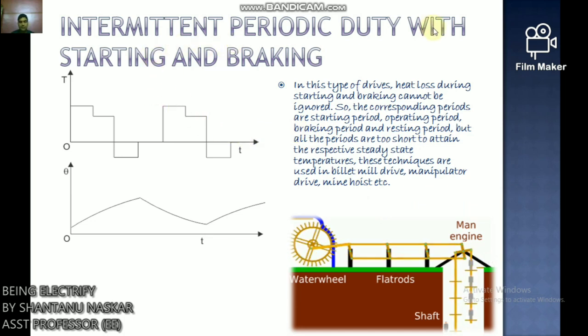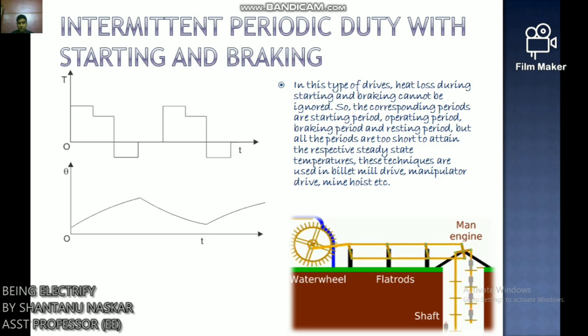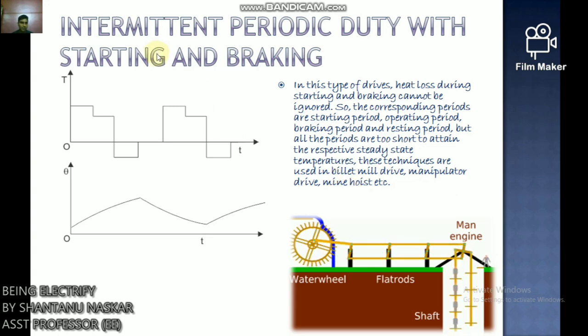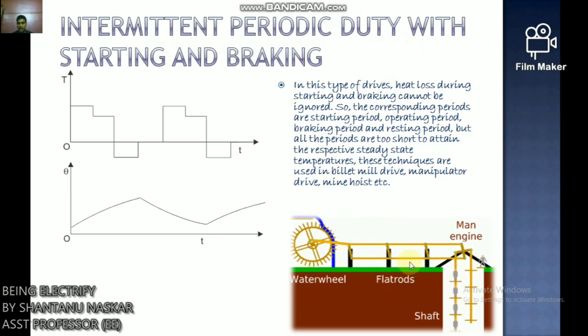Intermittent periodic duty with starting and braking: Heat losses during starting and braking cannot be ignored. The periods are: starting, operating, braking, and resting — all too short to reach respective steady state temperatures. These techniques are used in billet mill drives, manipulator drives, and mine hoists.